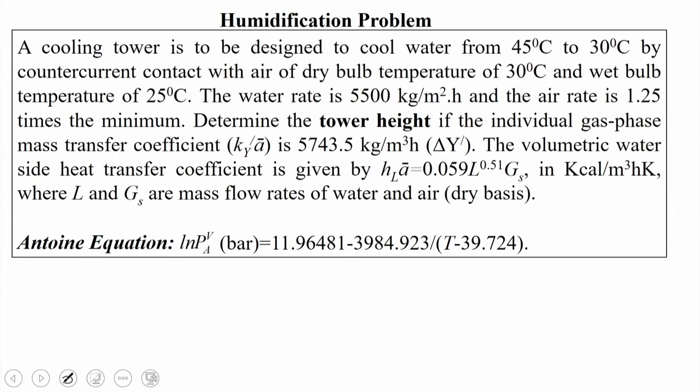The problem is: a cooling tower is to be designed to cool water from 45°C to 30°C by counter-current contact with air of dry bulb temperature 30°C and wet bulb temperature 25°C. The water rate is 5500 kg per meter squared hour and the air rate is 1.25 times the minimum. Determine the tower height if the individual gas phase mass transfer coefficient KY' prime is 5743.5 kg per meter cube hour.